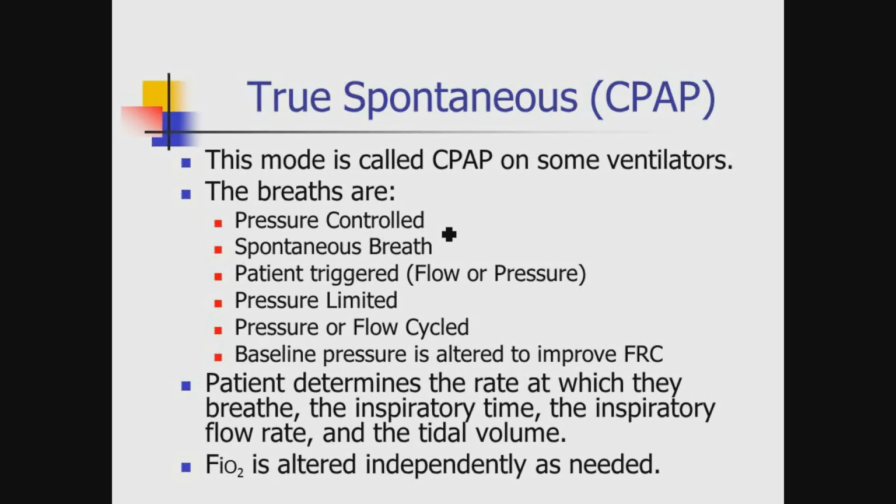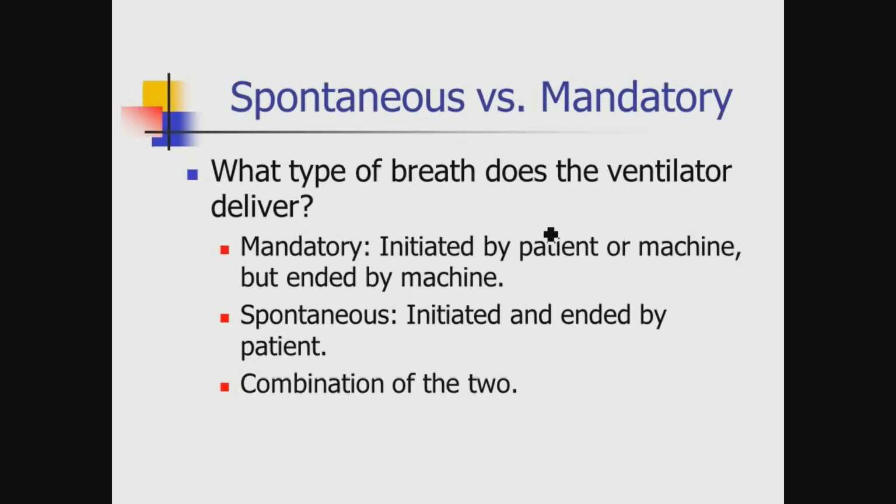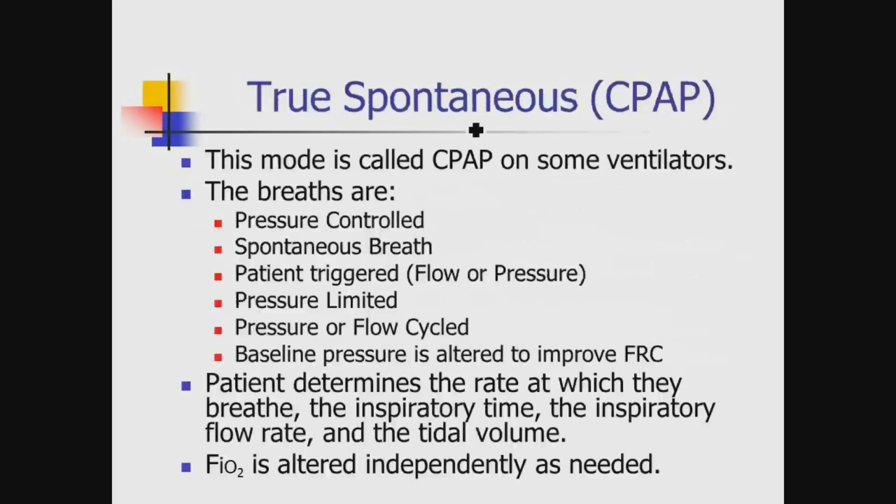So the pressure is what we're monitoring, the amount of baseline pressure that they end up having. They're basically breathing around a baseline. As they inspire, it goes down to a negative pressure. Exhalation becomes a positive pressure, but it's pressure control. We're the ones that are setting how much this baseline pressure is.